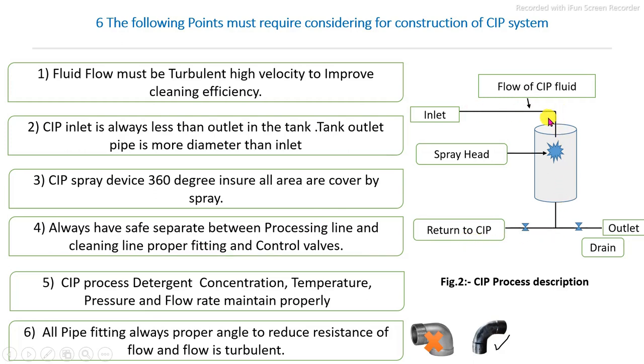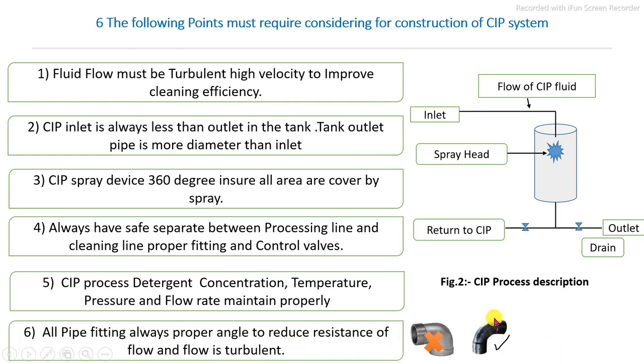There must always be a safe separation between the processing line and the cleaning line, properly fitted with controlling devices. Whatever the processing line system and the detergent circulation lines, these should be separate and properly fitted with controlling devices. In the CIP process, detergent concentration, temperature, pressure, and flow rate are automatically controlled by a microprocessor control system. All pipe fittings must always be properly angled to reduce flow resistance, and internal flow must be turbulent for proper cleaning of all piping systems.